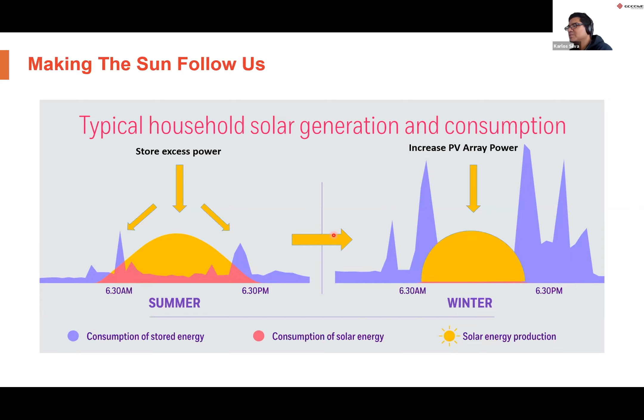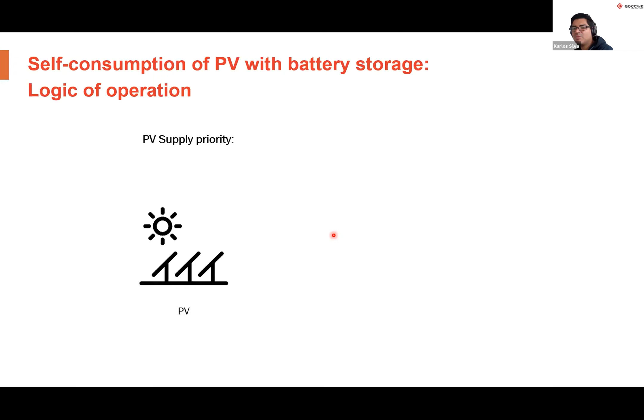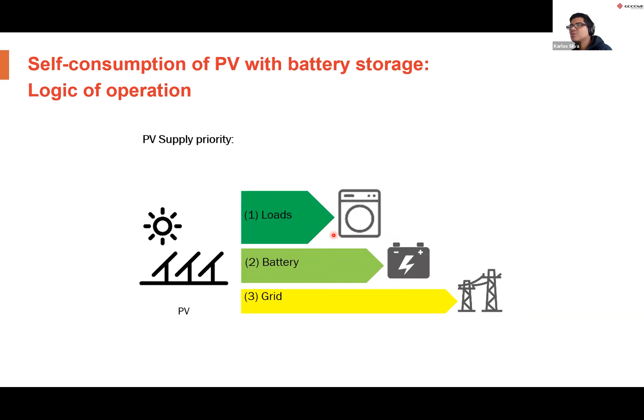So what is the logic of operation of a GoodWe hybrid inverter? Imagine yourself as a PV array: the power you produce will first be used to supply the loads. If you produce more power than required, the excess is sent to the battery to charge up to 100%. When the battery is full and there's still excess power being generated, this power is then fed into the grid. It's simple logic aimed at increasing your self-consumption.